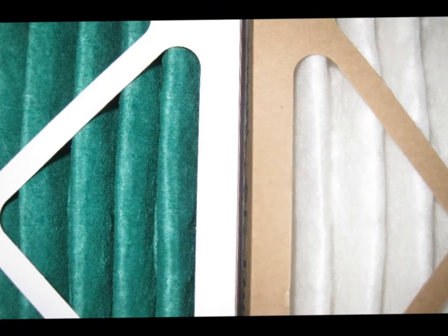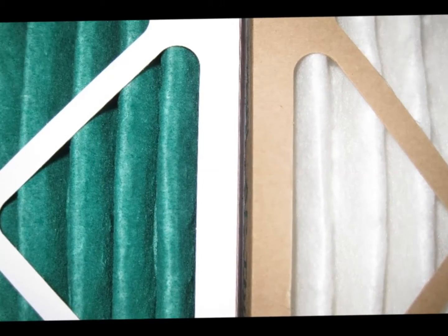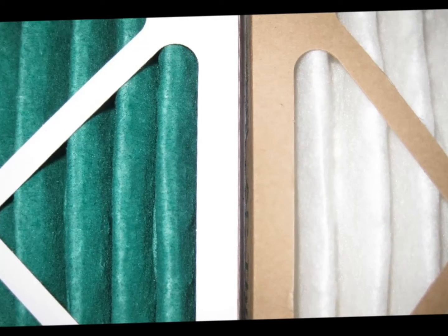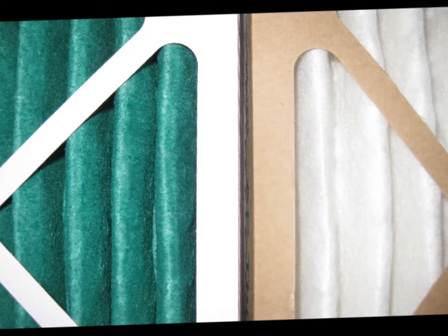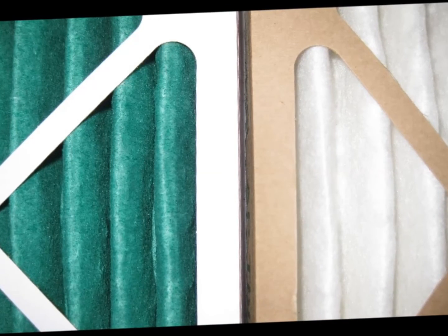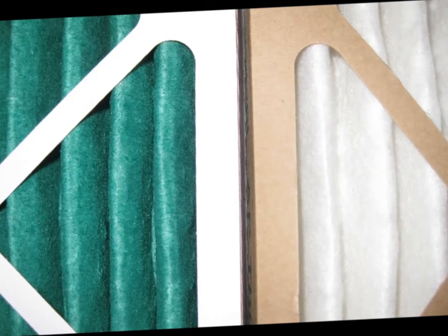Most pleated filters utilize a white beverage board frame that offers some protection against water, snow, and humidity. Kraft board frames, which are brown in color, are rarely used because they do not hold up well to the rigors a pleated filter must endure in an HVAC system.